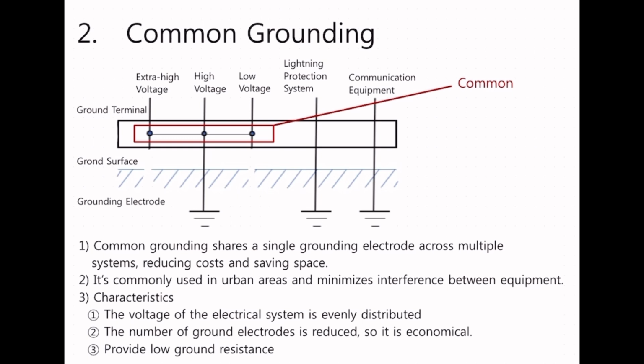Common grounding. Definition. Common grounding is a method where multiple systems, such as high voltage, low voltage, and communication systems, share a single grounding electrode. This approach is economical and saves space, making it popular in urban areas. System diagram. The diagram shows multiple pieces of equipment connected to a single grounding electrode, indicating that all equipment uses the same grounding point. Characteristics.